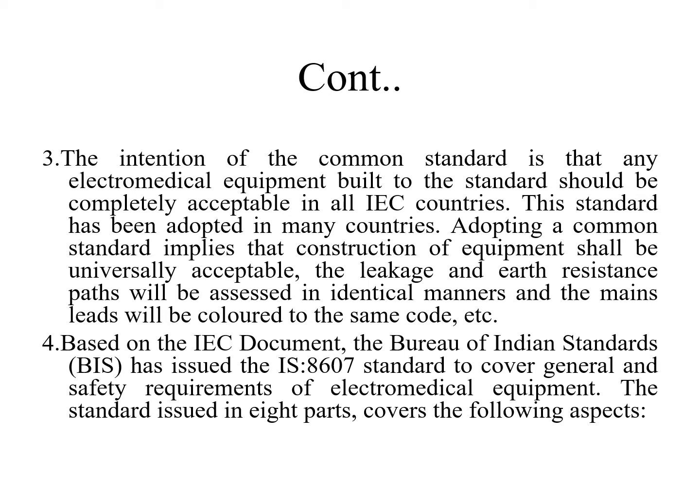Based on the IEC document, the Bureau of Indian Standards, BIS, has issued the IS 8607 standard to cover general and safety requirements of electro-medical equipment.